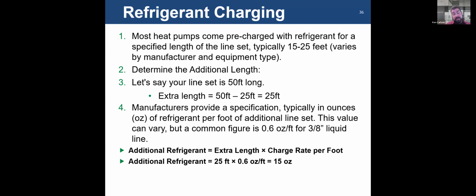You'll go to the manufacturer's installation instructions. They'll tell you exactly how much to add depending on the size of the line set, because that dictates how many ounces per foot you'll add. A common figure, typically for 3/8, 3/4 line set, is 0.6 ounces per foot. 0.6 times 25, you need to weigh in 15 ounces of refrigerant. That'll get you pretty close to your charge. With a heat pump, they only want you to weigh it in. You'll weigh in your 15 ounces, and that'll be it. You won't do anything else, most likely.